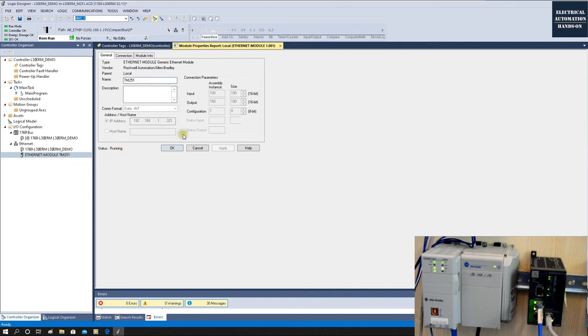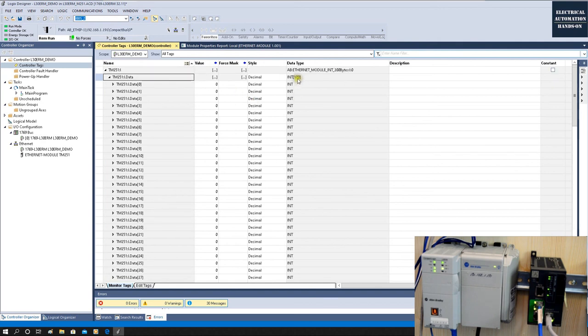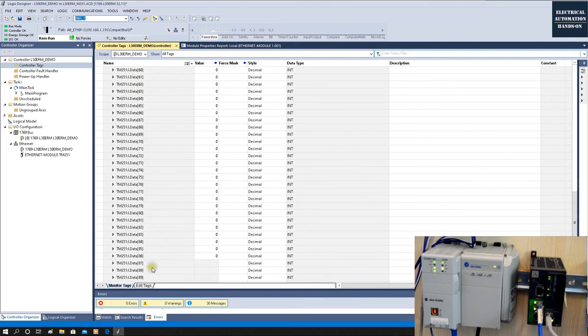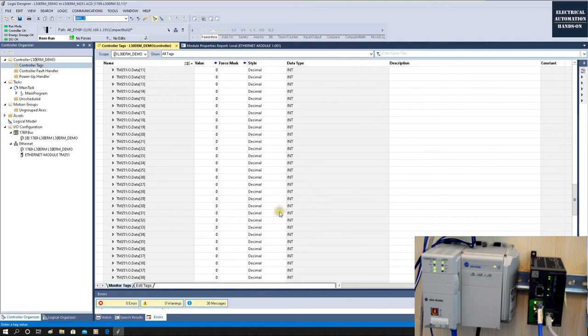Going online and double-clicking the generic module shows it as 'Running' — the controller is communicating with the Schneider Modicon TM251. In the Controller Tags, we can see the input array (Integer, 100 elements, index 0 to 99) and the output array (also 100 elements, 0 to 99). For testing, I'll set output[0] = 100, output[1] = 101, and output[99] = 199 to write values from the Allen-Bradley side to the Schneider side.